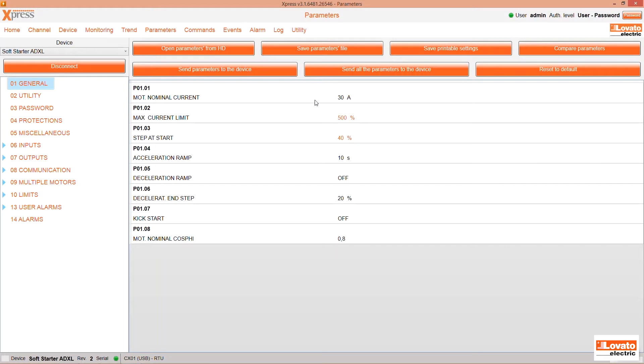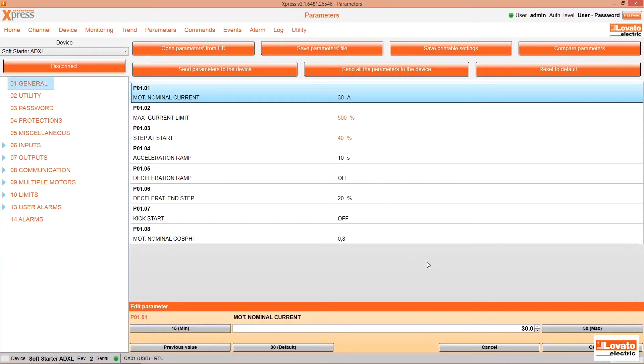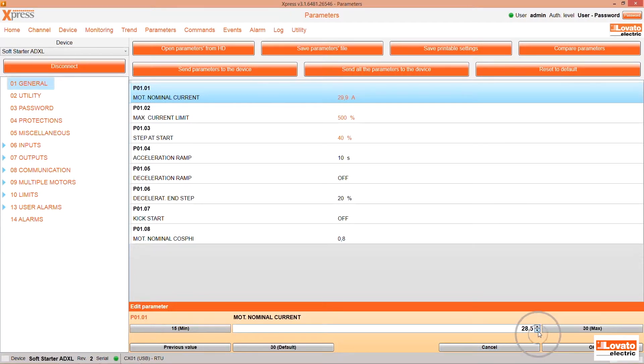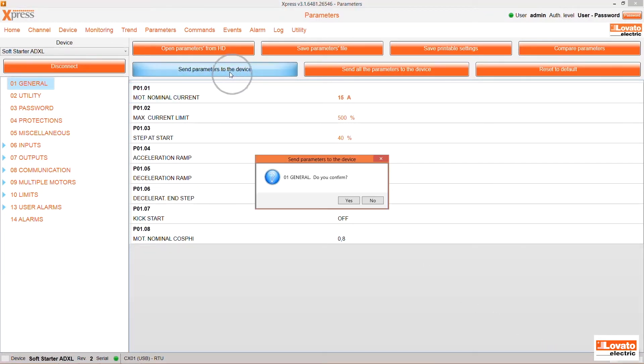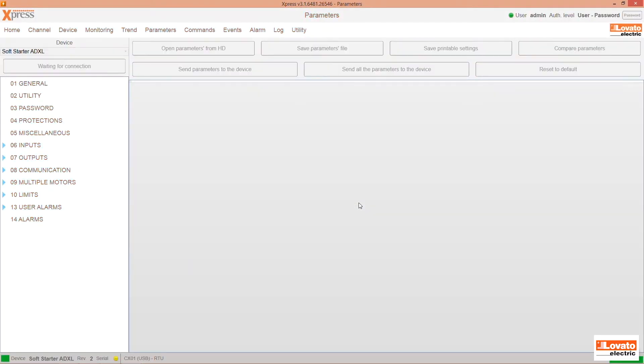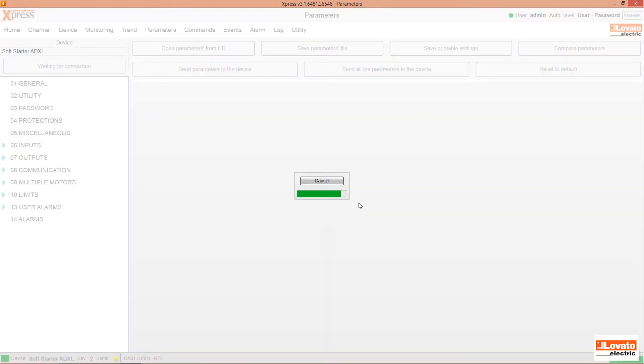Now you can change any parameter. Let's take, for example, the Motor Nominal Current. Click on the parameter, enter the desired value and press OK. You can send the single parameter to the device with Send parameter to the device, or send all the changes made with a single command by pressing Send all the parameters to the device.